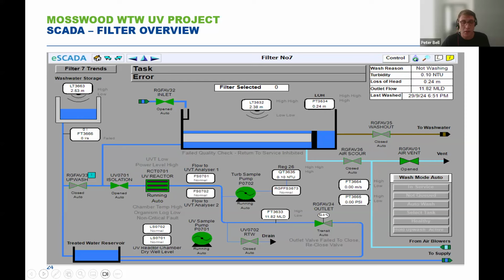We then had to build in the UV reactor, which you can see is indicating as running within the pipeline. We had analyzers put in there. We had to reprofile the pipework, etc. So we tried to make that look in a line diagram as close as we could to the actual physical install. But with this comes quite a task in itself. That isn't just a case of drawing that up and loading that in. You also have a lot of rules, inhibits, alarms, functions, etc., all built into SCADA so that it gives that overview.